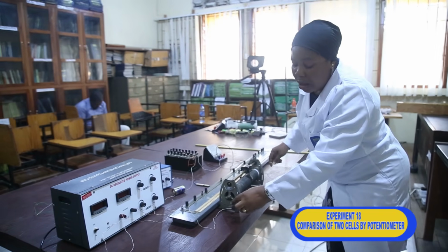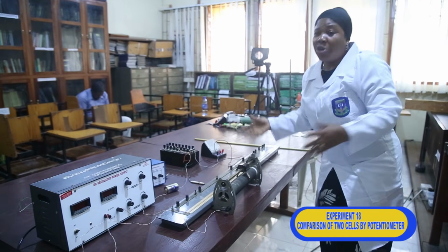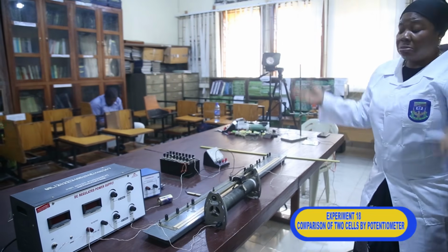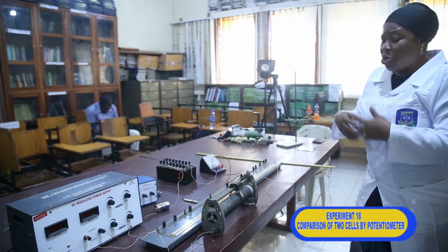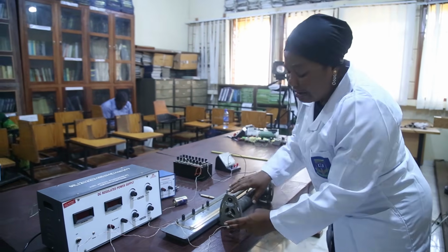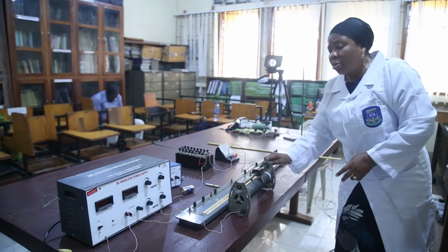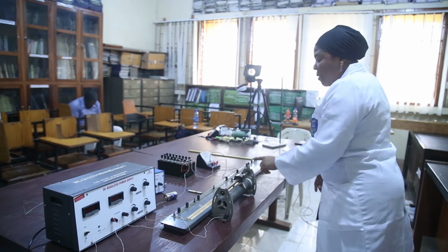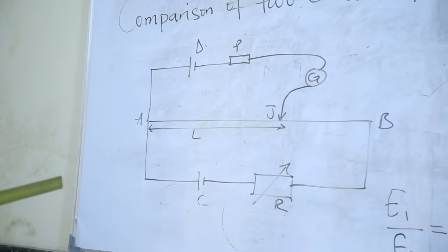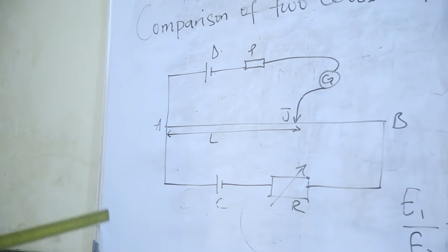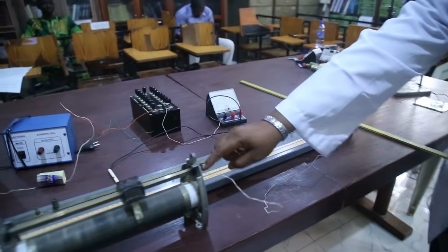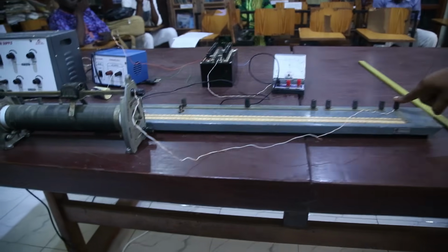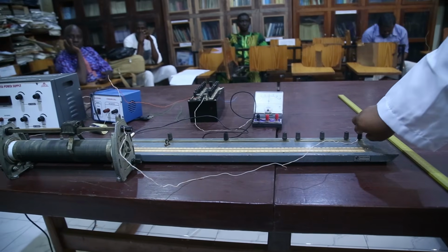If you connect at the lower point and you connect here, you're not going to get anything. You can keep connecting and trying all day and you won't get anything. So we connect to this side and you also connect to this other terminal here. From this terminal, from your diagram, you go towards B, and this is our B position. So you connect from here straight down to this point to give you the connection that we have there.